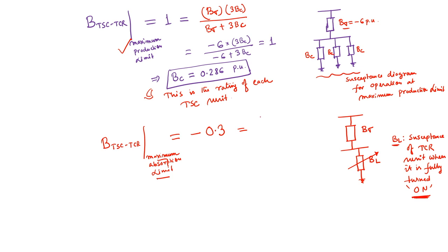If so, it will be equal to B sigma multiplied by B L, because they are in series, divided by B sigma plus B L. As we already know, B sigma is given as minus 6 per unit, so minus 6 B L divided by minus 6 plus B L equals minus 0.3. From this, one can find the value of B L, and as per my calculation it should be equal to minus 0.316 per unit.